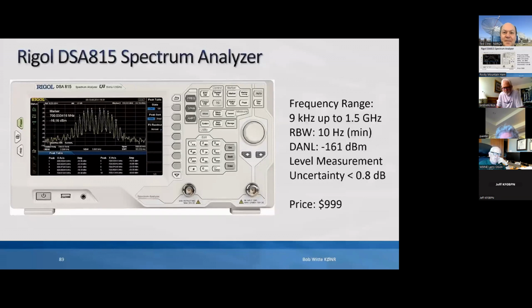So that's more of a bench kind of product. Certainly a lot higher price than the tiny SA, but they didn't spec dynamic range, but the DANL, displayed average noise level, was quite good. And then their resolution bandwidth, the frequency resolution, goes down to 10 hertz. So you can really zoom in and look at the fine details of a signal, the spectral content of a signal.